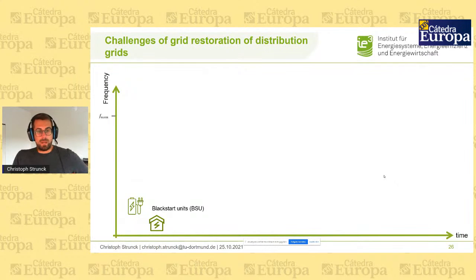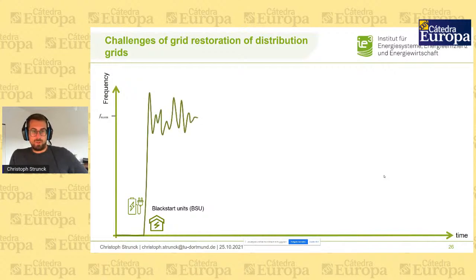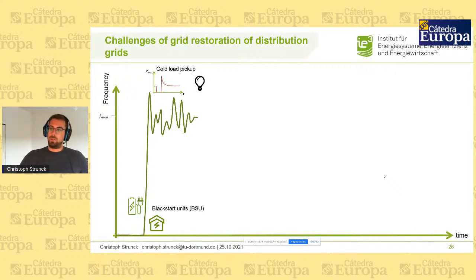First, we need some black start units, which can be a battery storage or a CHP plant. Then we try to connect some loads and assure a certain frequency. Here we need to consider effects like cold load pickup from the loads - after a blackout we have a higher load than before, due to a diversity factor for fridges or air conditioning or similar.